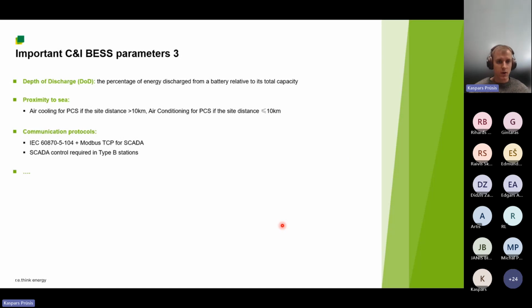And also important factors are communication protocols. For C&I solutions that are up to 499 kilowatts of output power, we don't need communication to SCADA in Latvia, to SCADA DVS, but for solutions which have output power of more than 499 kilowatts, we need, of course, communication with SCADA, so that's important. There are also other parameters that are important, but we shall not discuss them here so that we don't overload you with the information.